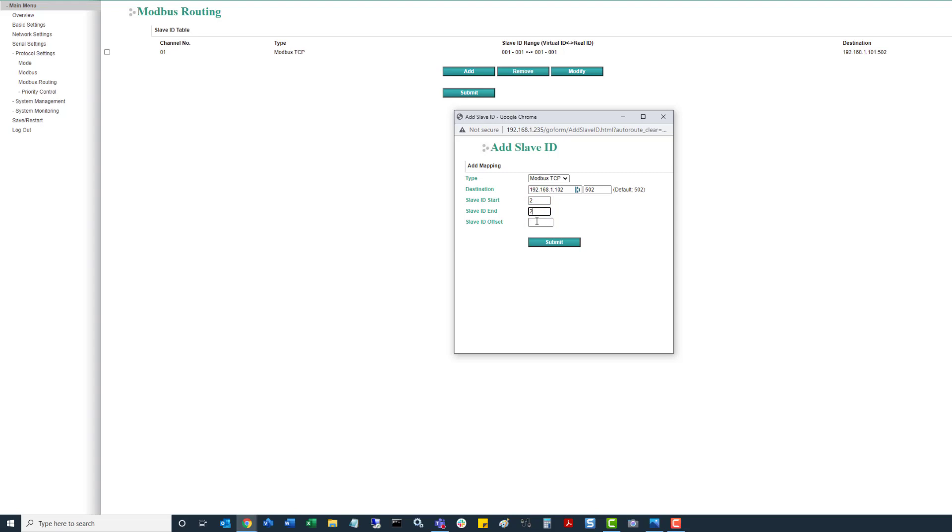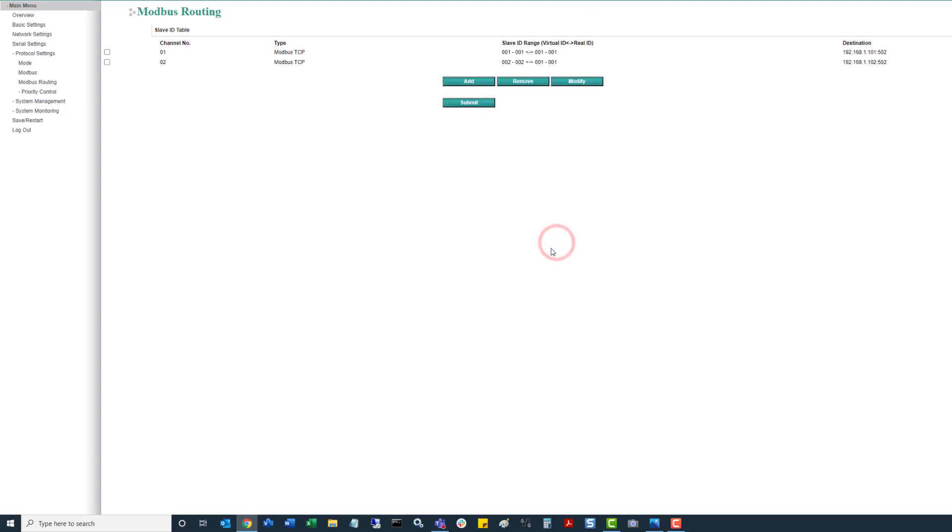But we're going to offset it. So when it actually goes to route and connect, we're requesting slave ID 2 from the master unit. But then when it goes out to talk to the actual field unit, it's going to be looking for ID 1. So that's where when we want to offset it by one, we just set that by one. Click on submit.